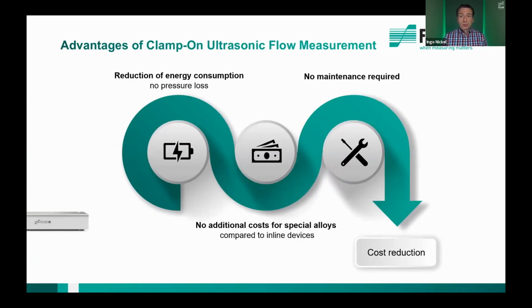Furthermore, ultrasonic flow meters can help reduce costs. I think it's nowadays important for all of us to reduce energy consumption. And by using ultrasonic flow meters, we can reduce it because we install a system which generates no additional pressure loss. This means we do not lose any power of our pumps, because we are not inserting any kind of device into the pipe. And if we are working with corrosive media, the non-invasive approach removes the need for cost-expensive alloys or other expensive material for the wetted parts.